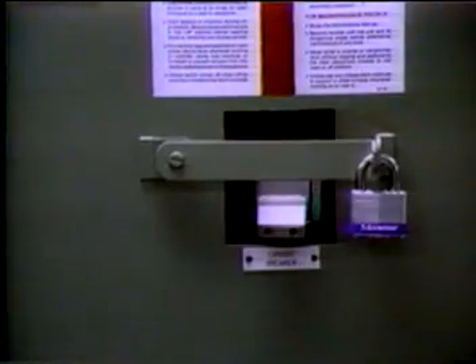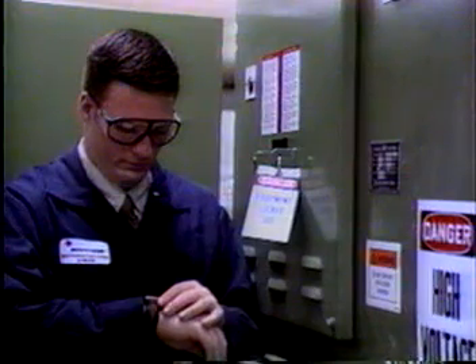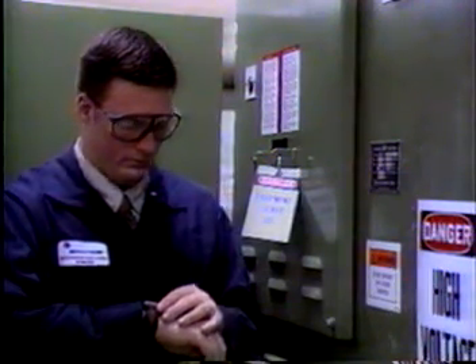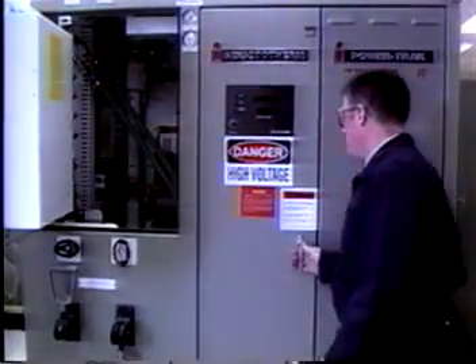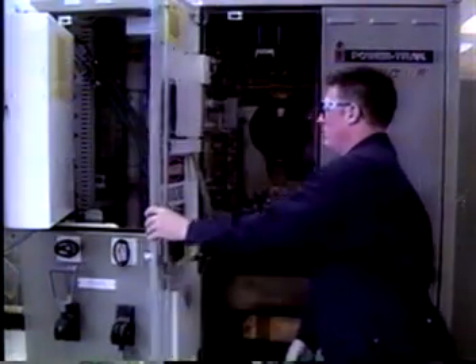Remember, forbid entry into any enclosures until the main circuit breaker is locked in the off position and breaker poles are confirmed to be open. Even then, wait 5 minutes after opening a breaker before opening cabinet doors. This allows capacitors time to discharge harmlessly. Next, test all bus bars for residual voltage before touching anything.